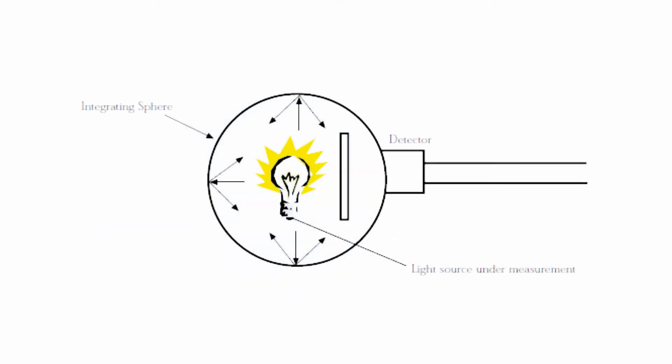There are ports on the sphere for instruments, samples, and light sources. The light source is placed in the sphere and a measurement is taken with either a photometer for photometric measurements or a radiometer for radiometric measurements. The sphere would initially be calibrated with a standard light source, so the reading from the photometer or radiometer indicates the total light power.